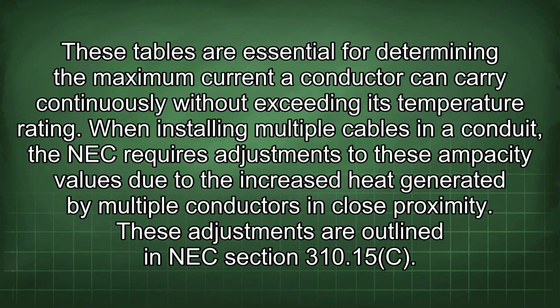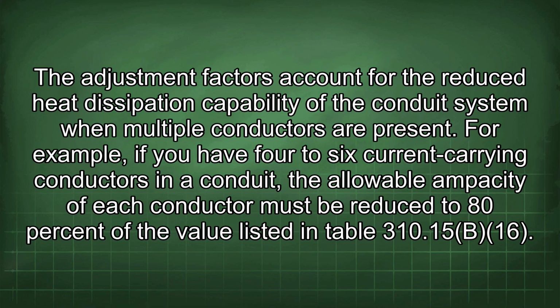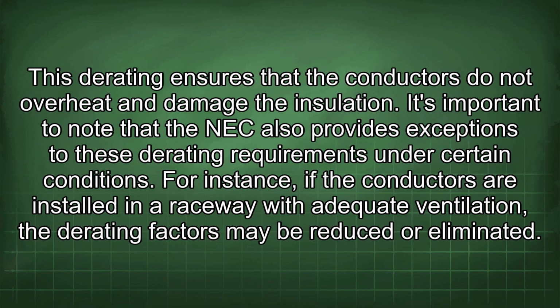When installing multiple cables in a conduit, the NEC requires adjustments to these ampacity values due to the increased heat generated by multiple conductors in close proximity. These adjustments are outlined in NEC section 310.15(C). The adjustment factors account for the reduced heat dissipation capability of the conduit system when multiple conductors are present. For example, if you have 4 to 6 current-carrying conductors in a conduit, the allowable ampacity of each conductor must be reduced to 80% of the value listed in Table 310.15(B)(16). This derating ensures that the conductors do not overheat and damage the insulation.